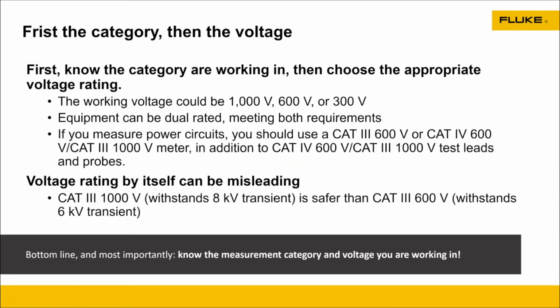So again, know the voltage ratings of where you're at and what you're doing, and the category rating of what you're doing. A category 3 meter that's rated for 1,000 volts can withstand an 8,000 volt transient. That spike we were talking about earlier, very critical. It's actually safer than a category 3 600 volt meter that can only handle a 6,000 volt transient. So the bottom line on this is just really know where that measurement category is.